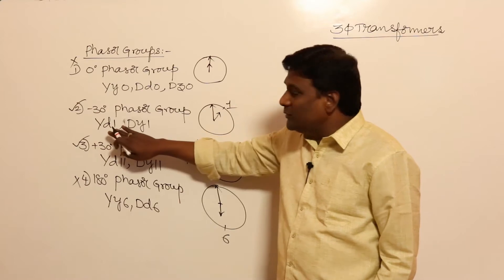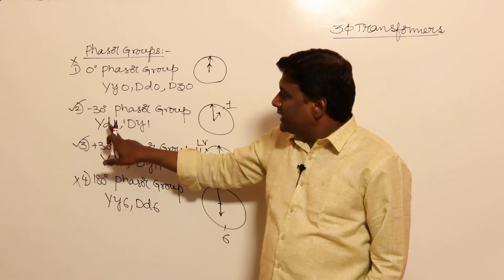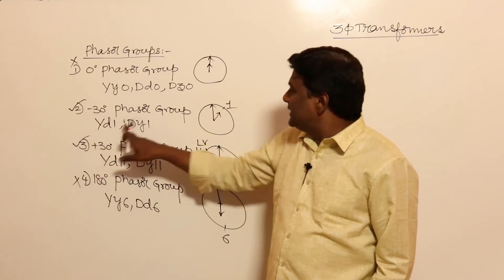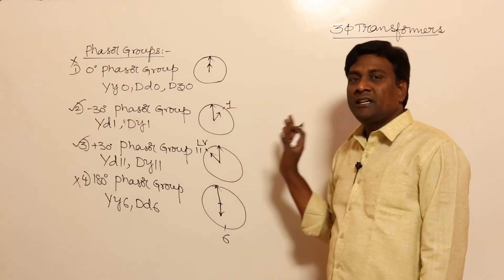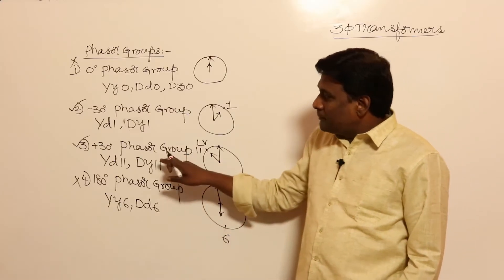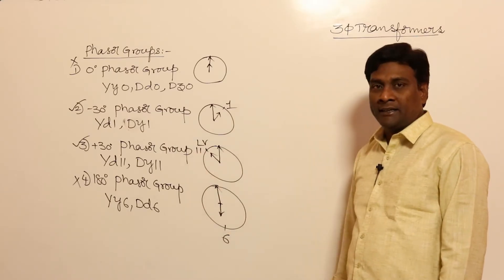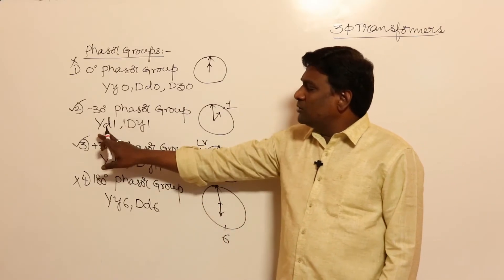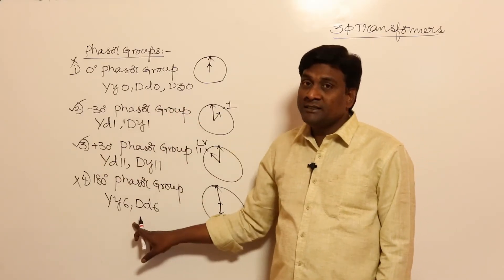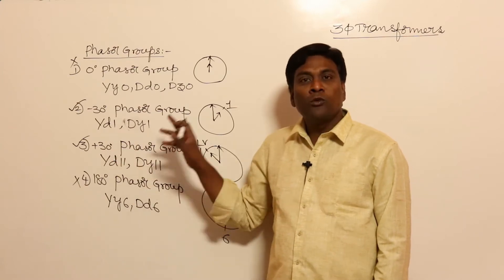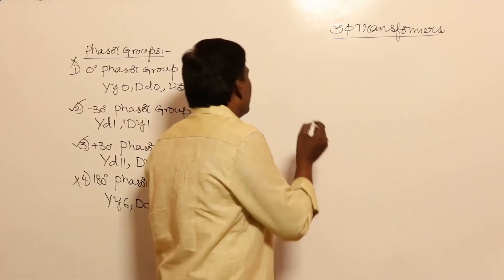For us, only two important phasor groups matter. YD1 means HV is connected in star, LV is connected in delta, and displacement is 1 — meaning LV line EMF lags behind HV line EMF by 30 degrees. Plus 30 degrees means LV line EMF leads HV line EMF by 30 degrees. In the exam, for YD connection, YD0 and YD6 are not possible — only YD1 and YD11 are possible, so two options can be directly eliminated.